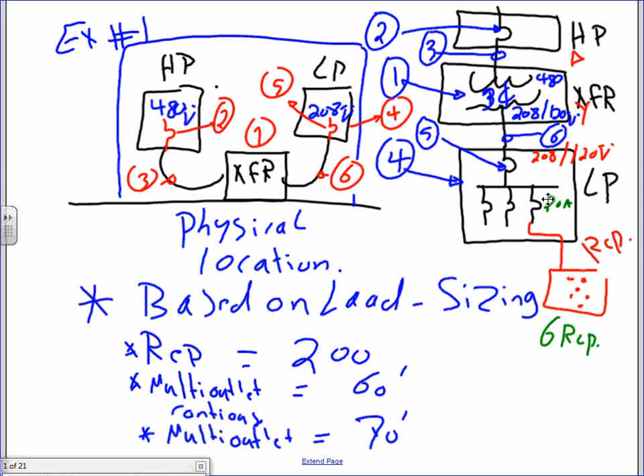You guys have done 2 load calculations with your friend. Remember when we did that calculation for the receptacles, we based it on the number of receptacles first, we did a calculation, then the multi-outlet assembly, right? So this is the electrical load that you have. That's my load. This is the most important thing. Based on the load, I need to size all these. Any comments, any questions about what we have? Does it make sense? We have 200 receptacles, 60 feet of multi-outlet assembly, like the one in front of you, continuously used, which is important because if they're continuously used, we allocate a different value for them than if they were not.